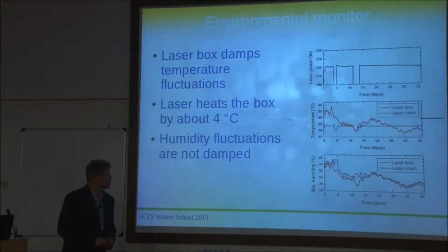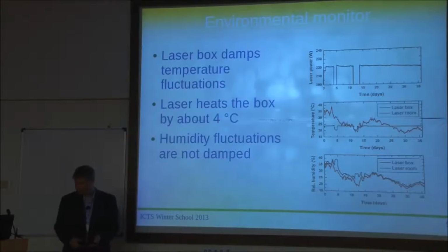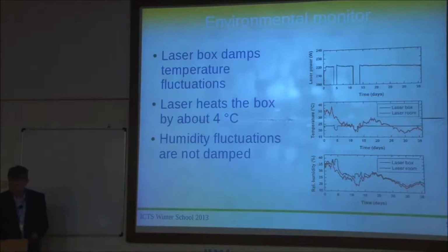However, that's not true for the relative humidity in the room. That's not damped by the laser box, so it's not really tightly sealed. You can see that the humidity inside the laser box actually follows the humidity in the room where the laser is placed.